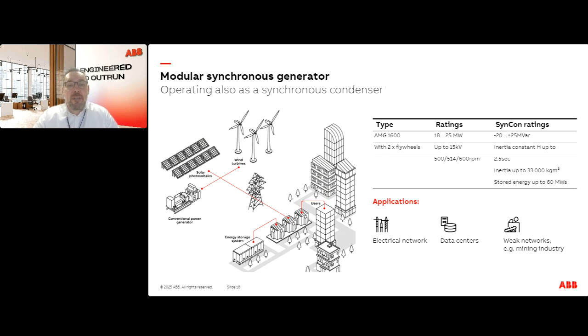And then, as I mentioned, this generator can also be used as a synchronous condenser. So what is a synchronous condenser? It's not a motor, it's not a generator, it's basically a machine that runs in synchronism with the grid and provides reactive power and also rotating inertia. Because, like Luca also mentioned, energy transition means that there will be a lot of solar and a lot of wind installed in the networks. Those power sources don't have the natural inertia which the grid needs to remain in synchronism and operate reliably.